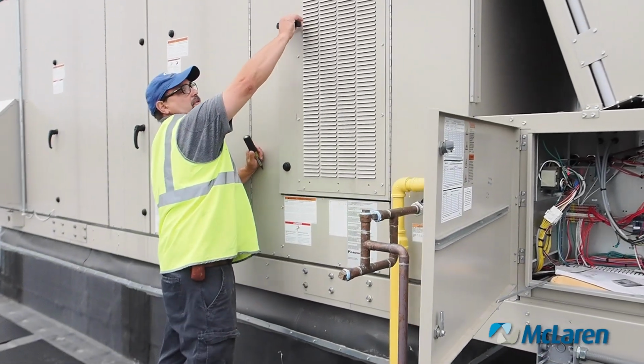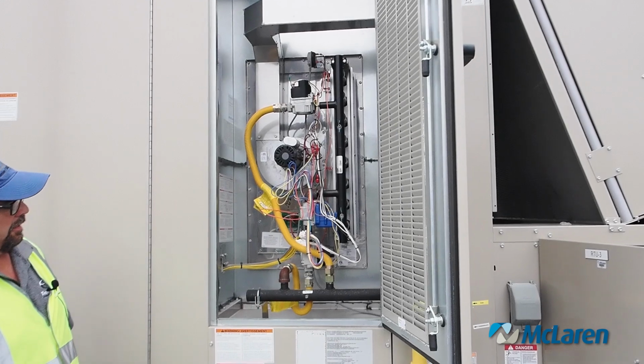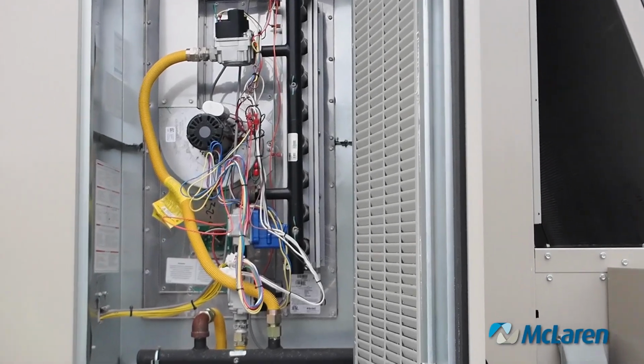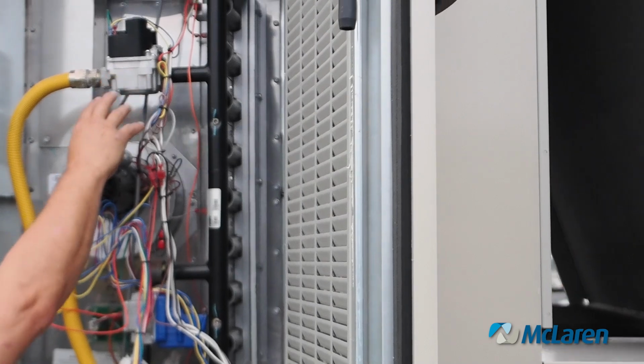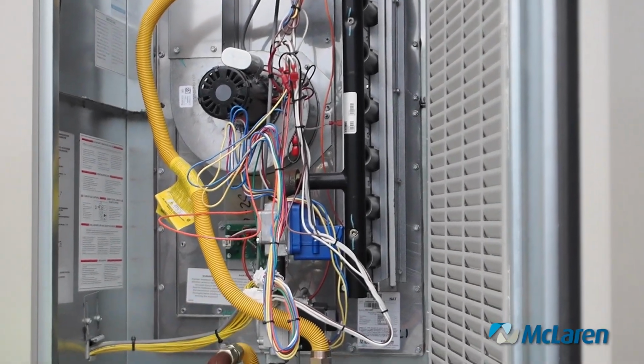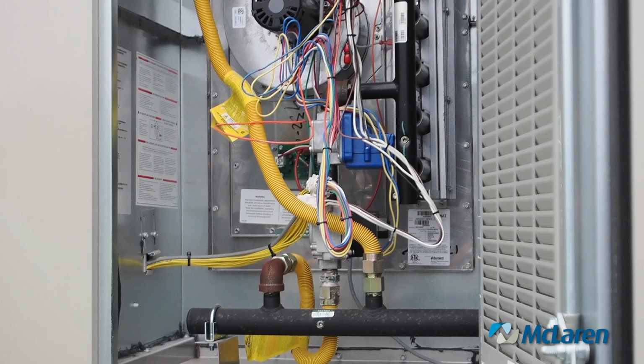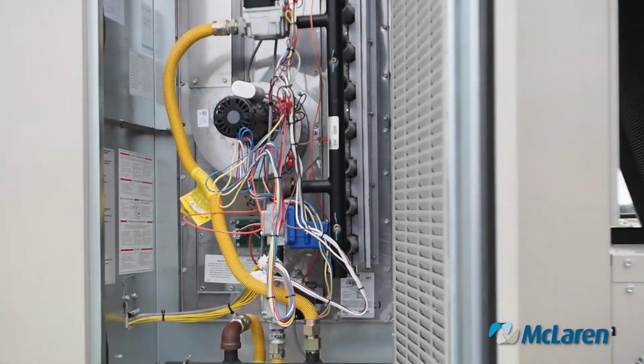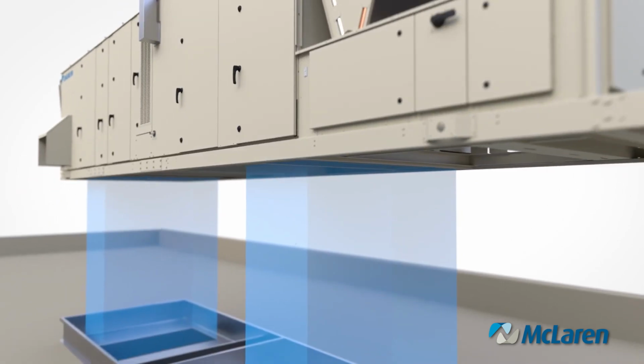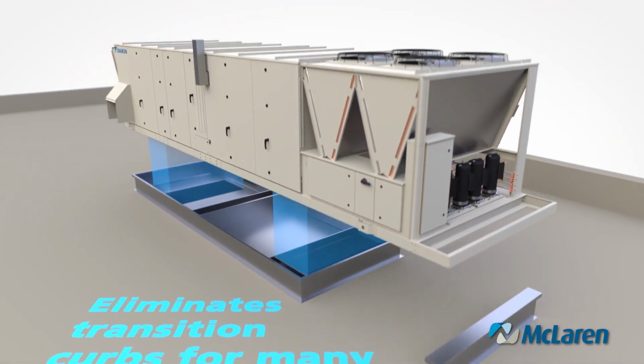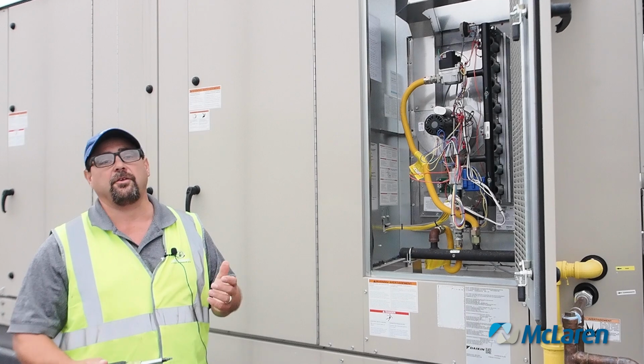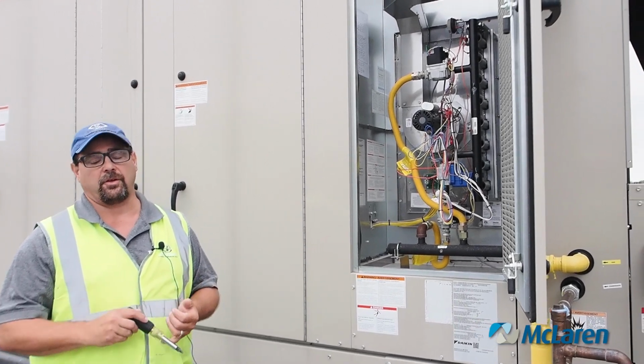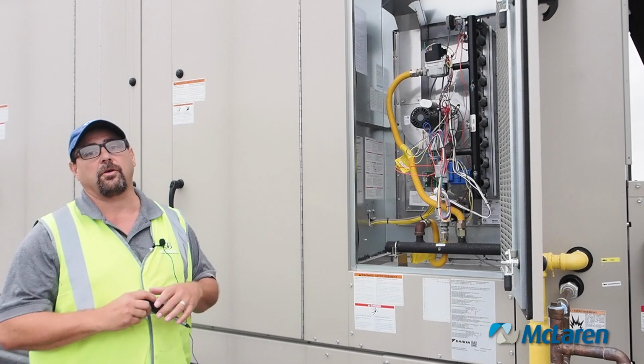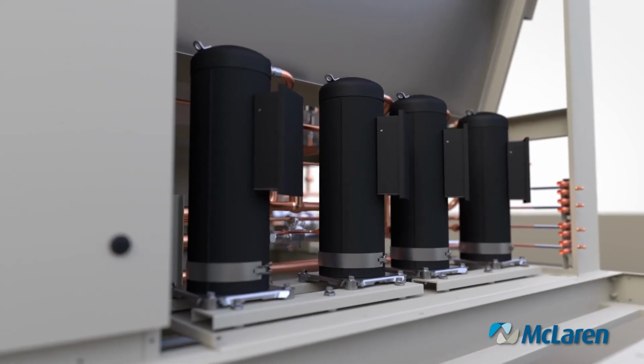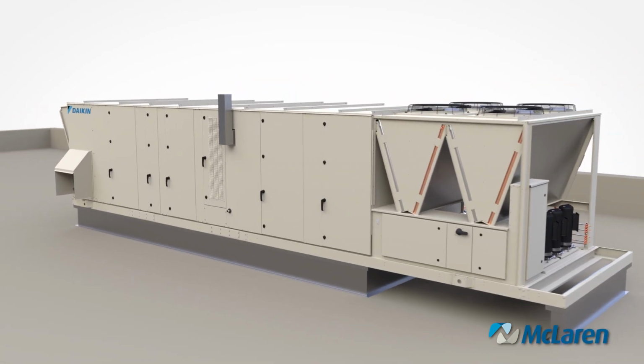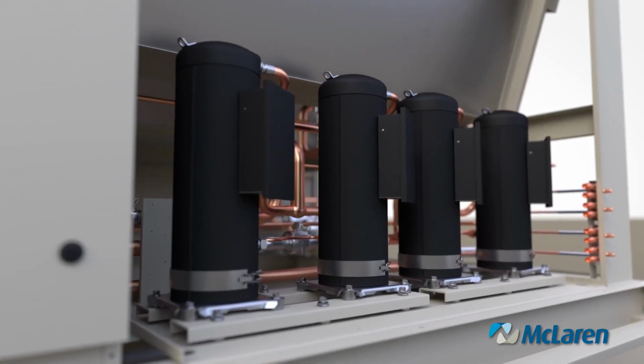This is our gas burner section of our rooftop. This operates two burners. One is a high and low up here. One down here is a modulating burner. So there are times where you're going to see very little flame coming out and times when you're going to see this thing go full capacity. I believe it's based on discharge air temperature that will require that operation. And just like any direct fired burner, you're going to eventually have to clean the sparker, electrode, maybe wash the burners. Just a fine piece of sandcloth or a wire brush to clean all those up. Or if you're not comfortable doing that, you can call ThermalNetics for the parts and just replace them as needed.